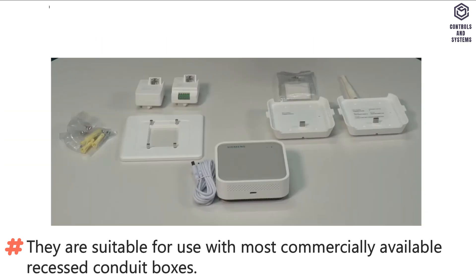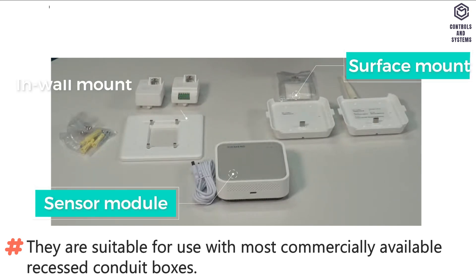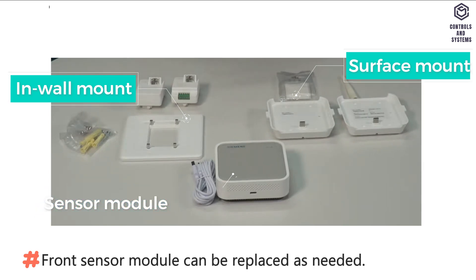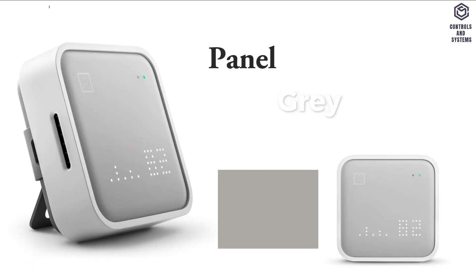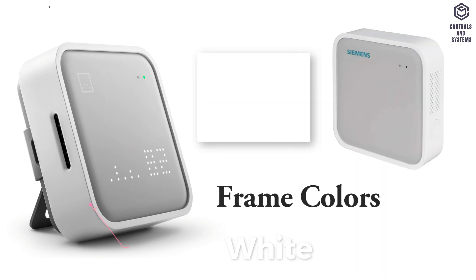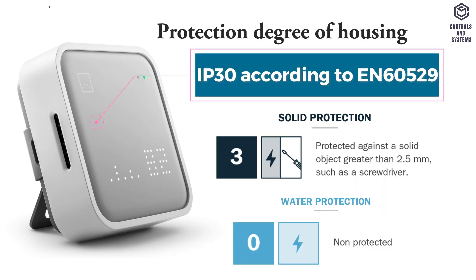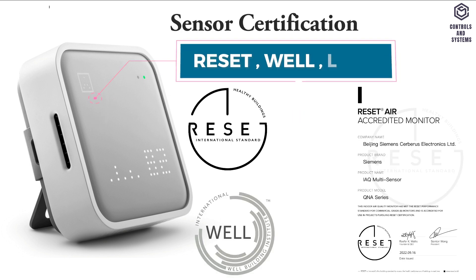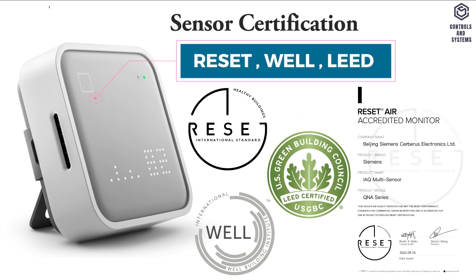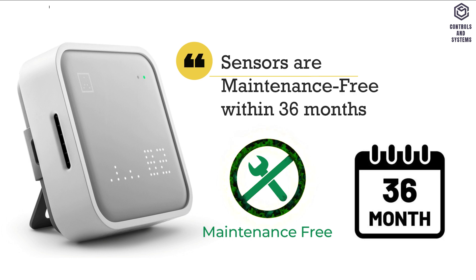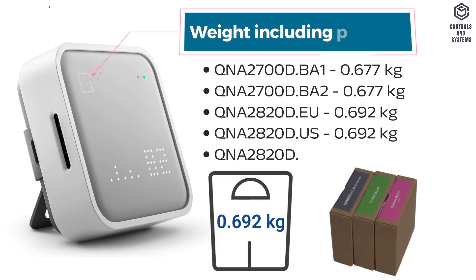The device has three parts: Sensor Module, Surface Mount, and In-Wall Mount. The front Sensor Module can be replaced as needed. Material data: Panel color is gray, frame color is white, protection degree of housing is IP30. Sensors are maintenance-free within 36 months. Weight is 0.692 kg including package.